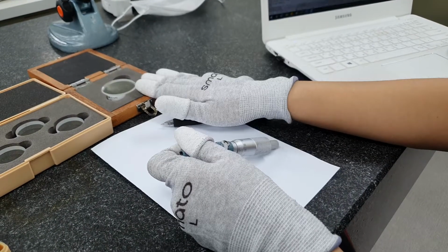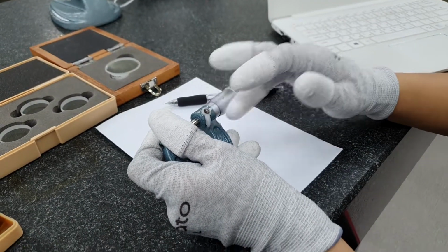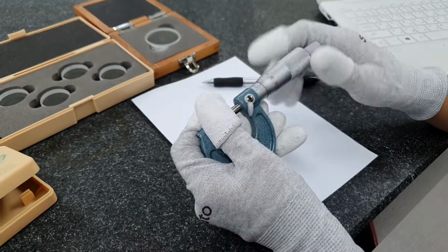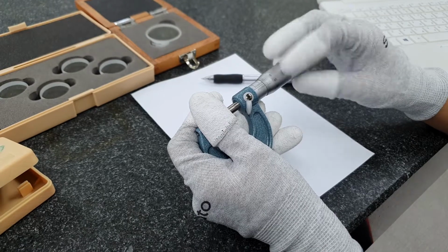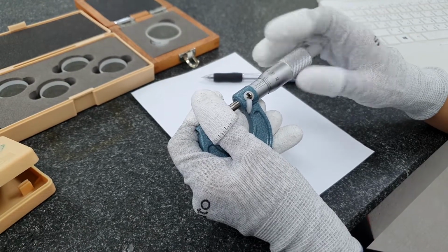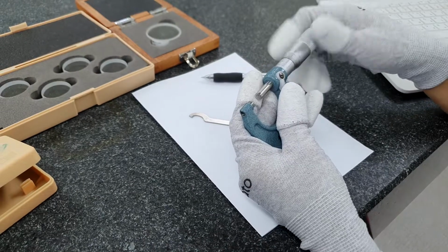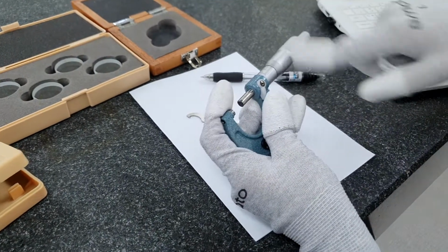The flatness test is to read the number of the red interference patterns of a white light source after inserting it between the pressure foot. Then measure the anvil and spindle and multiply by half the wavelength of light. I will put the flatness at here.